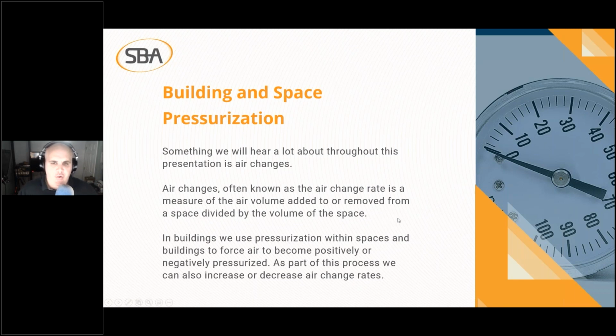So you hear like 3 to 4 air changes an hour for an average space. You'll hear 20 to 30 air changes an hour for an operating room. And how we control that is we will often use pressurization within our spaces and buildings, and that will create a positively or negatively pressured space. A positively pressured space pushes the air outside the space. So you'll see this in ORs, where we want to push the air out of the operating room into the standby corridor where they're staging all the surgery gear and whatever it is they do. And then we have negatively pressurized spaces.